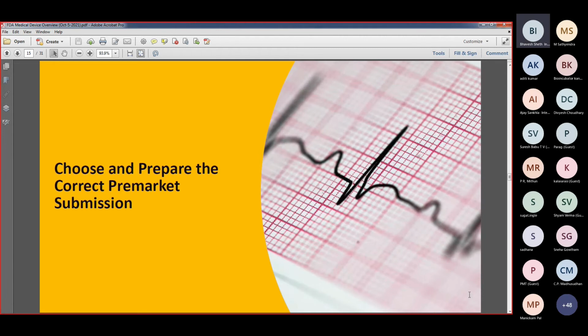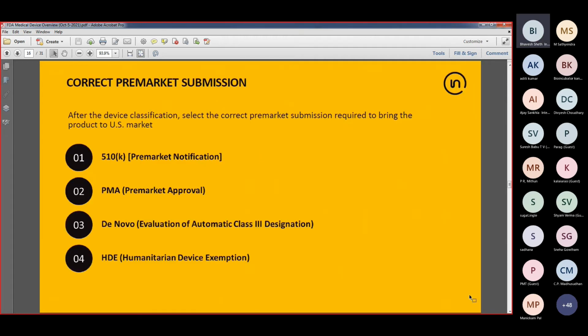So once you've classified your device, you choose and prepare your correct pre-market submission. So now we have to consider what all different types of submissions are possible, pre-market submissions in particular. So here we have 4 main types of pre-market submissions. The first one is 510K, which is also called a pre-market notification. The second one you see there is a pre-market approval. The third one is a De Novo, where it says evaluation of automatic class 3 designation, but I'll explain a little more about that category. And the last one is a humanitarian device exemption. So these are the 4 main types of pre-market submissions that could be made to the FDA depending on the device classification.